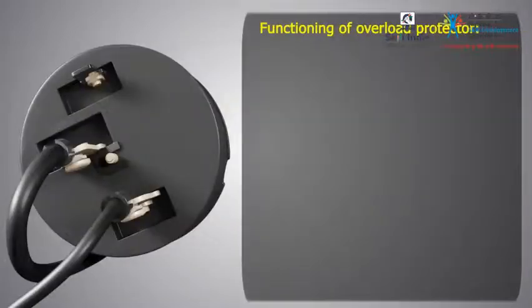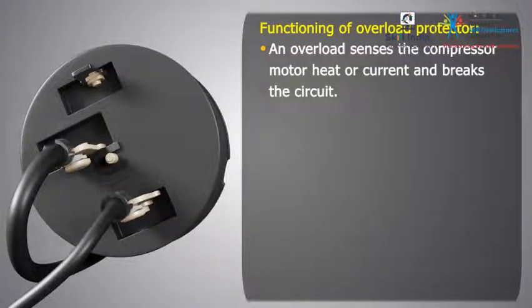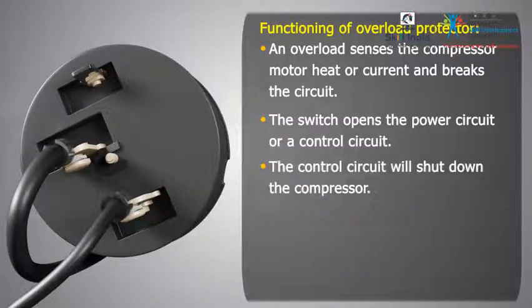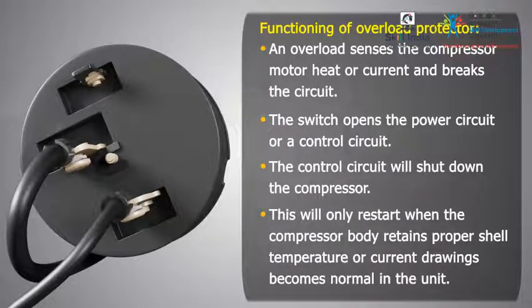Let me explain its functioning. An overload senses the compressor motor heat or current and breaks the circuit. The switch opens the power circuit or a control circuit. The control circuit will shut down the compressor. This will only restart when the compressor body retains proper shell temperature or current drawings become normal in the unit.